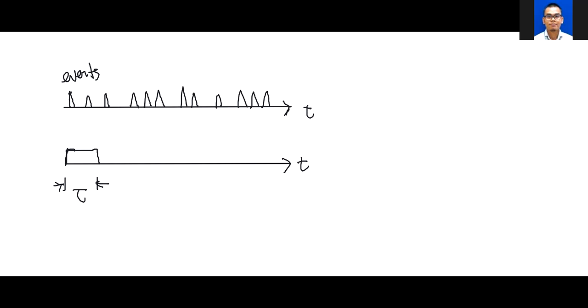So in the first event, when the detector detects the interaction, the detector cannot detect the second event here because it is still within the dead time interval. So the second event is not recorded. So the system will not count the second event.